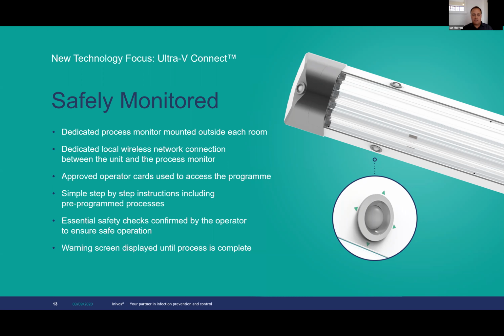The essential safety checks are confirmed by the operator, and then there's a warning screen displayed until the process is complete. So it's very clear the process monitor is mounted outside the room, it's clear the decontamination is in process, and there's a clear set of safety instructions checked by the operator.